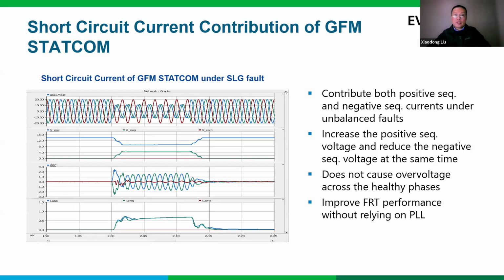Also, its voltage source behavior counteracts the voltage changes, which is similar to a synchronous machine. So on an unbalanced fault, the grid forming STATCOM intends to increase the positive sequence voltage while decreasing the negative sequence voltage. The traditional grid following STATCOM doesn't contribute any negative sequence current, as we know, unless it is specially designed with a current boosting capability. However, the grid forming STATCOM inherently has a feature with improved fault performance.